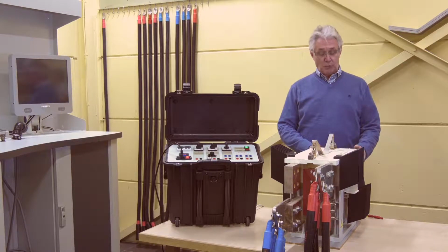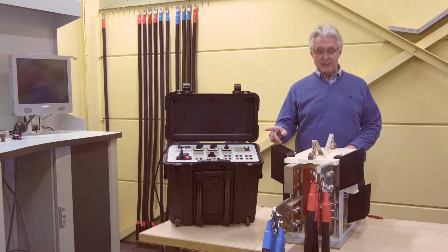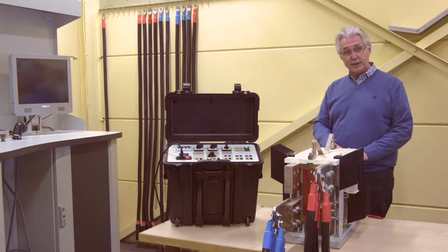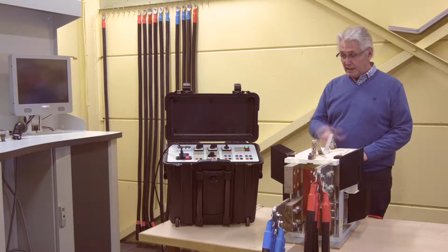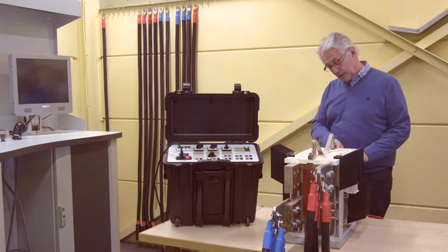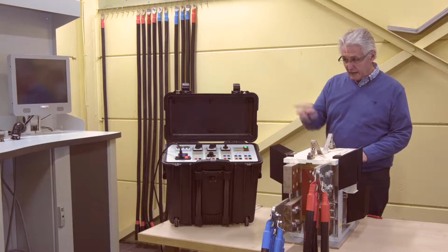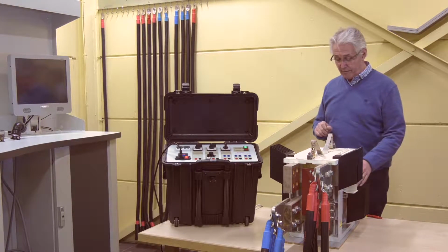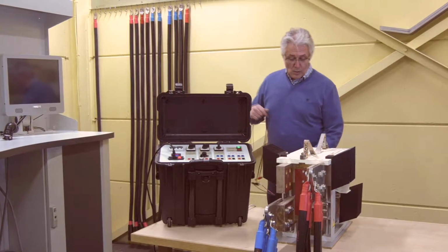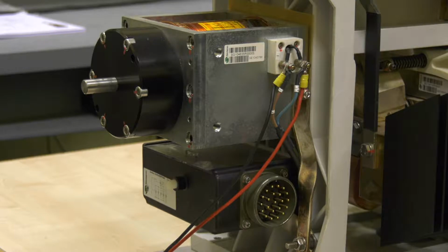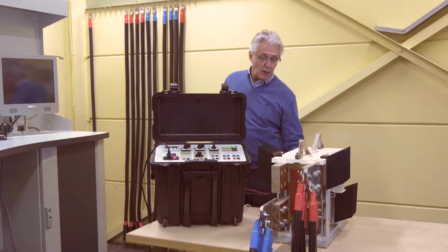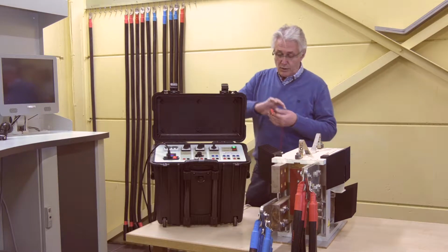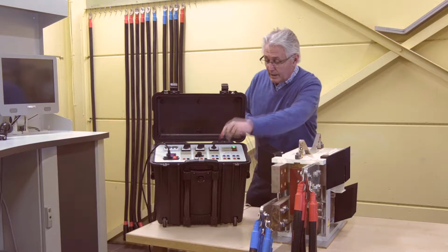At the back of the circuit breaker you can find the coil, and we need to connect the coil to the BCD. Make sure that the voltage, which you can read on the coil, is in line with the voltage of the BCD. So it reads 110 volts and our system is also set at 110 volts. We have connected the electrical cables here directly to the coil. In a professional environment you should do this via the connector which is mounted on the circuit breaker. So let's connect the coil of the breaker to the BCD.